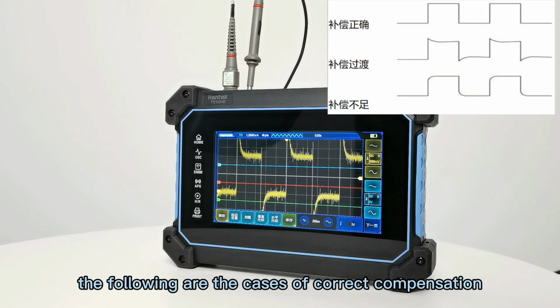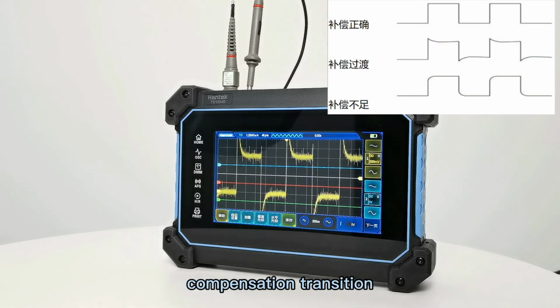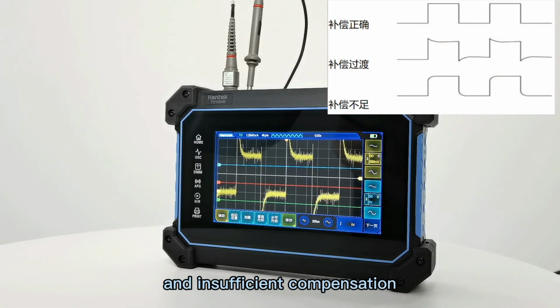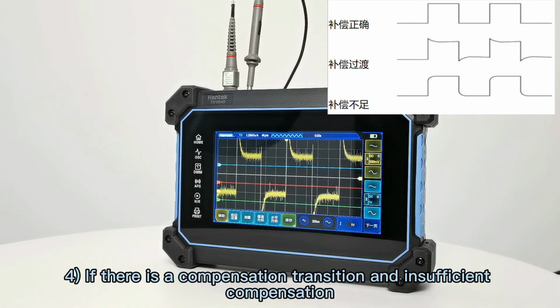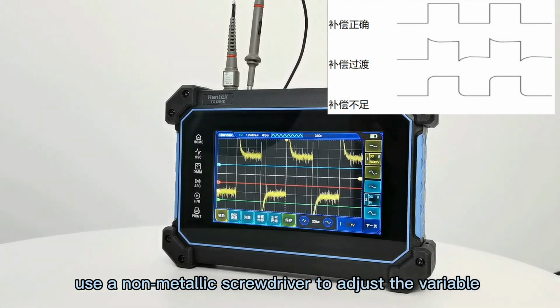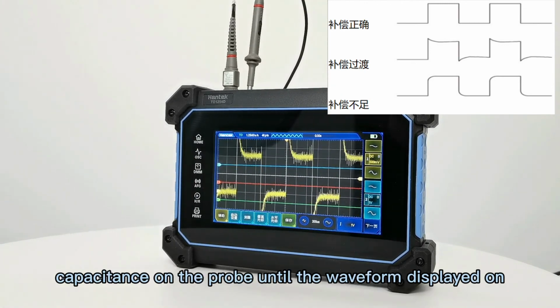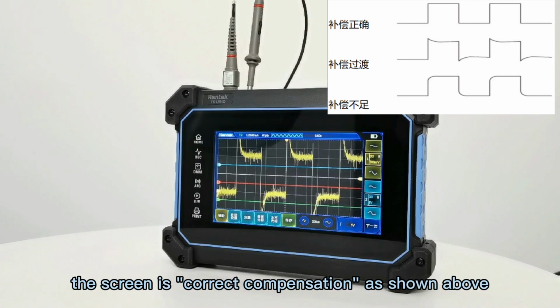The following are the cases of correct compensation, compensation transition and insufficient compensation. 4. If there is a compensation transition or insufficient compensation, use a non-metallic screwdriver to adjust the variable capacitance on the probe until the waveform displayed on the screen is correct compensation, as shown above.